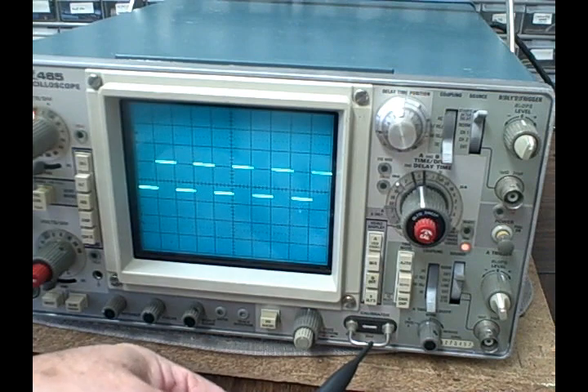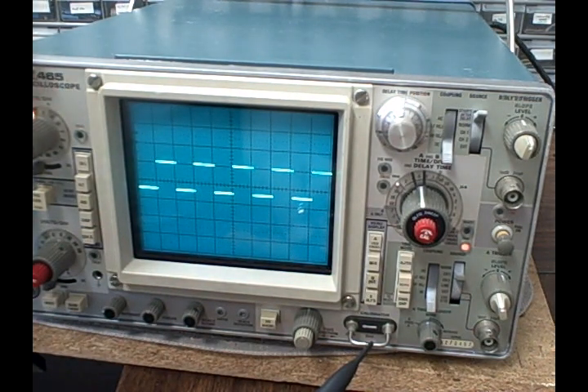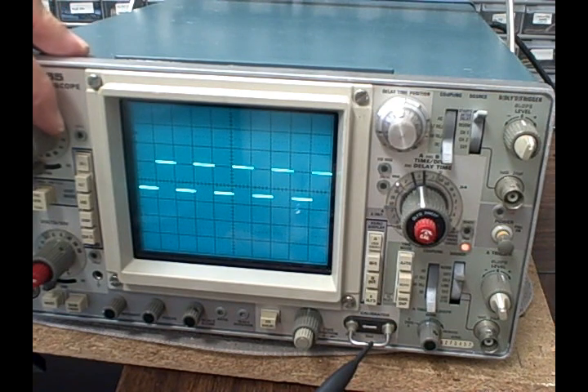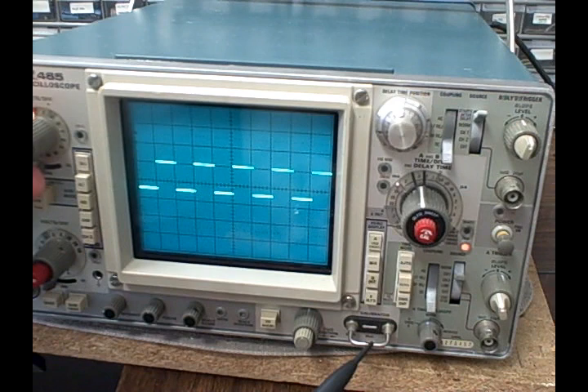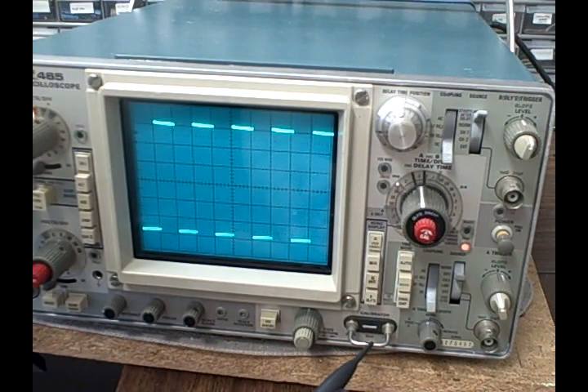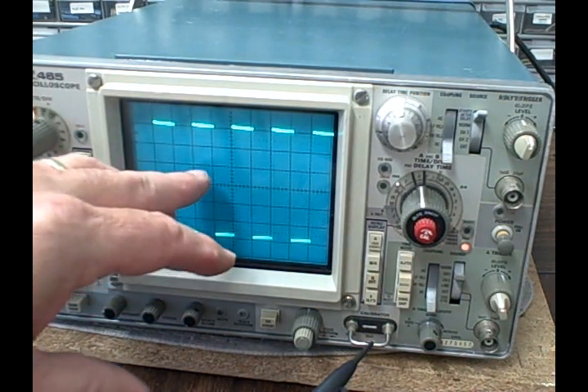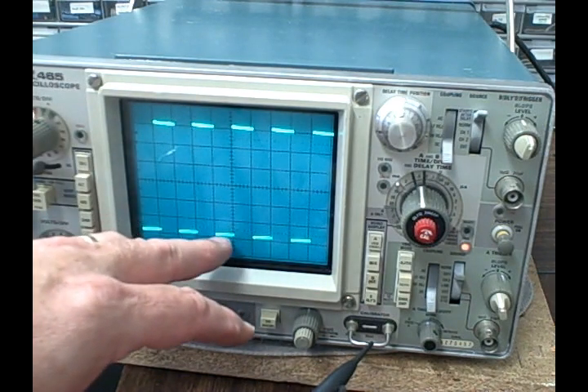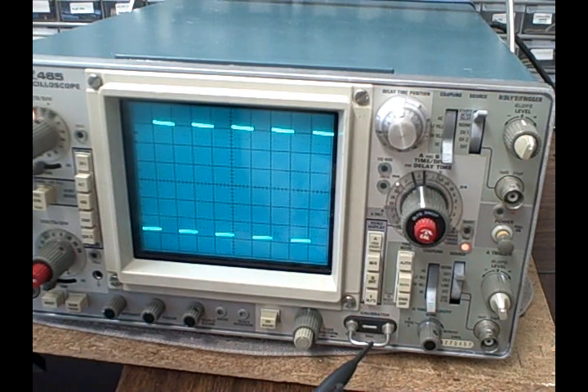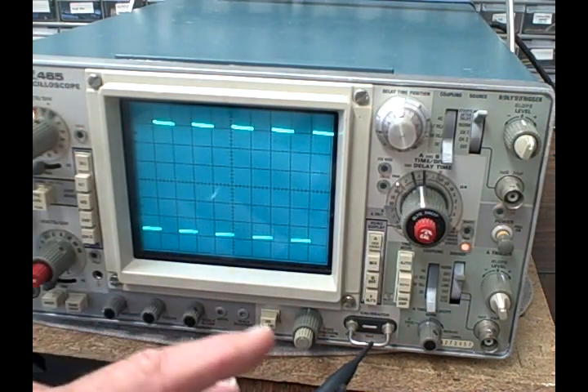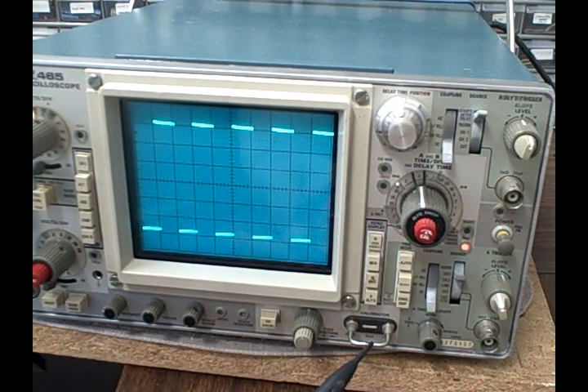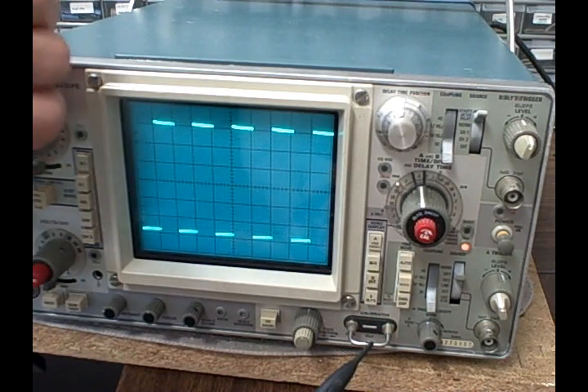Now we also are in the 20 millivolt per division position right now. Now if I went to the 5 millivolt per division, I got 1, 2, 3, 4, 5, 6 times 5 would be 30 millivolts peak to peak, and I'm supposed to have 300 millivolts, but then again I've divided by 10, so 300 divided by 10 would be 30. So the 30 millivolts is correct in this position.